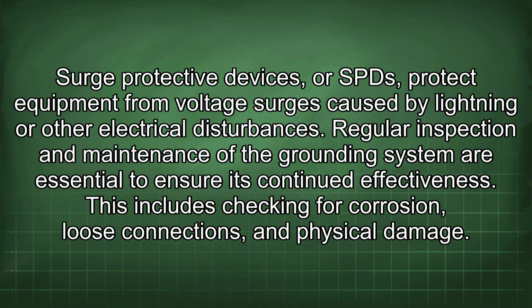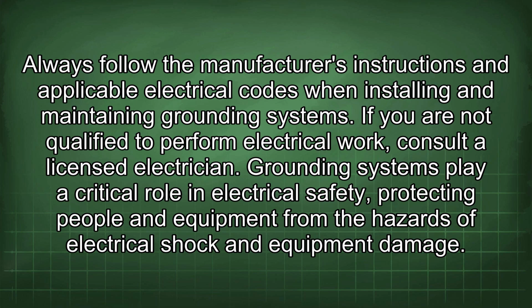Regular inspection and maintenance of the grounding system are essential to ensure its continued effectiveness. This includes checking for corrosion, loose connections, and physical damage. Always follow the manufacturer's instructions and applicable electrical codes when installing and maintaining grounding systems. If you are not qualified to perform electrical work, consult a licensed electrician.